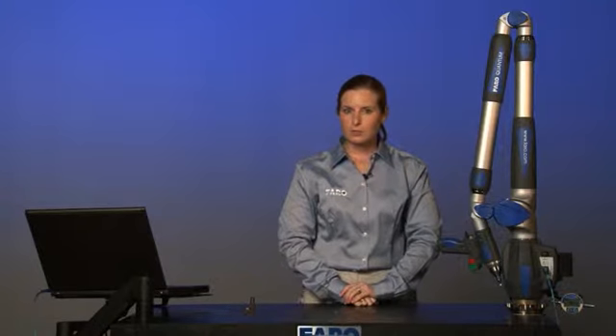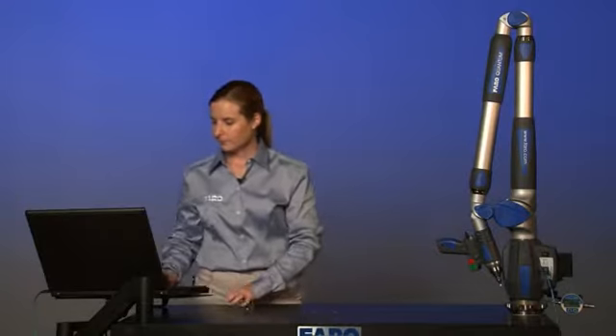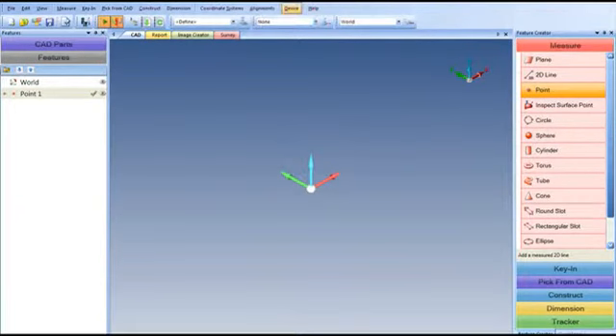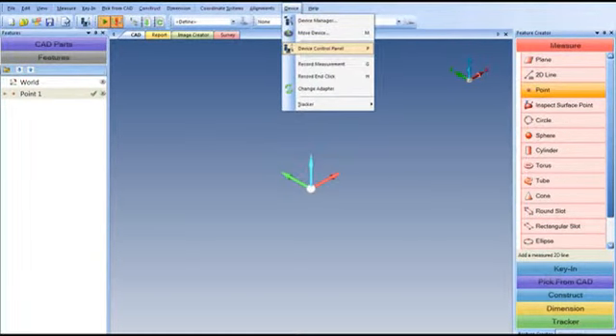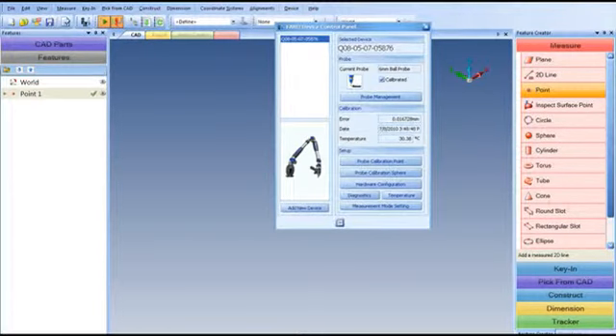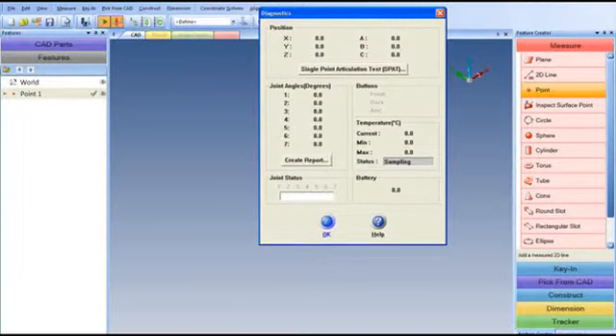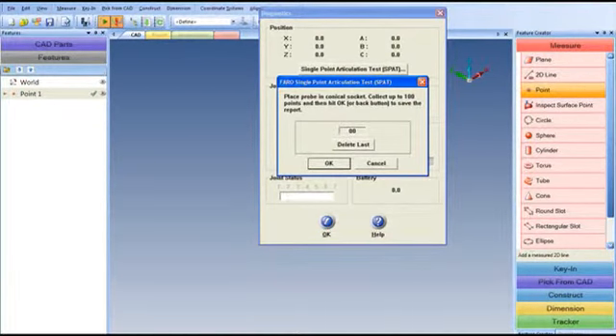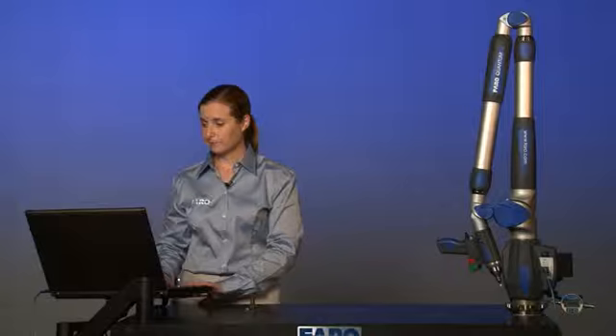Our next step is to check the accuracy of the arm itself. For that, we use something called a SPAT test. SPAT stands for Single Point Articulation Test, and you can find it in the software under the Devices menu. In the software, go to Device and Device Control Panel. Select Diagnostics, and near the top of the window you see Single Point Articulation Test. Click the button, and now the software is prompting you to collect data.